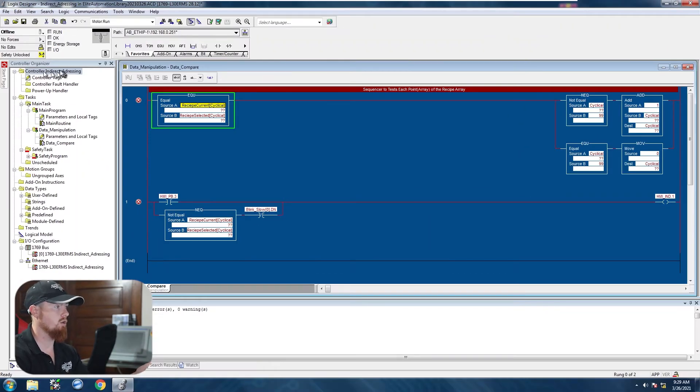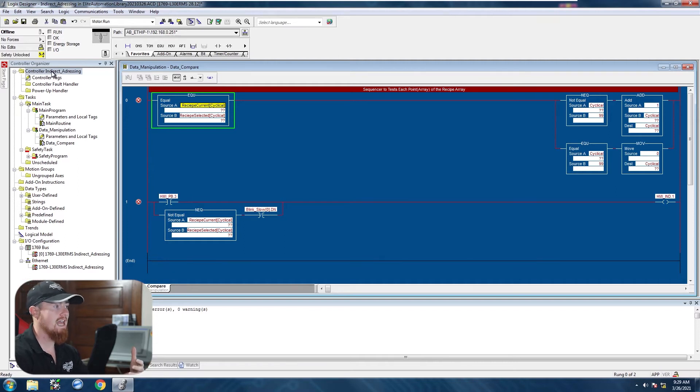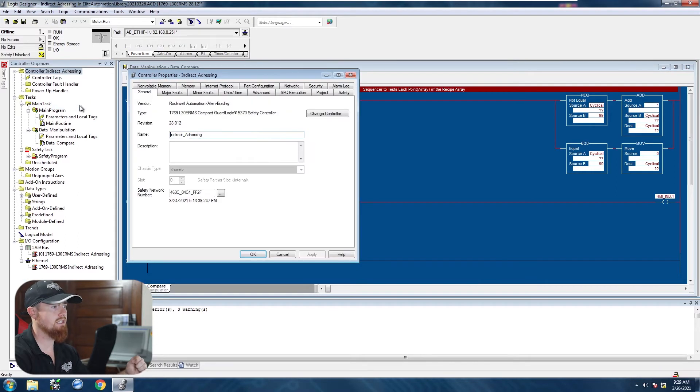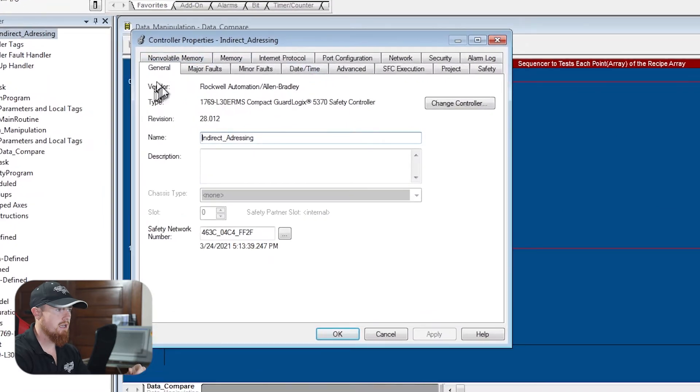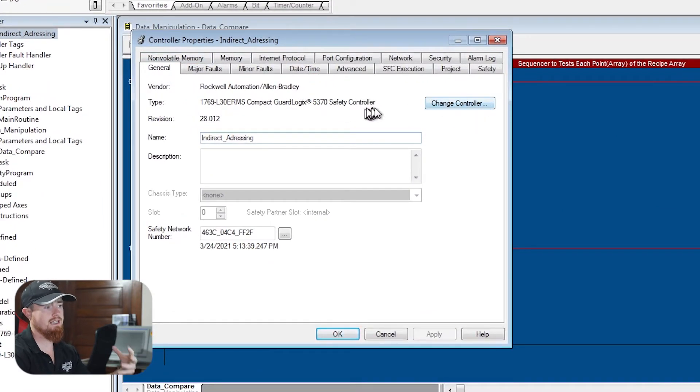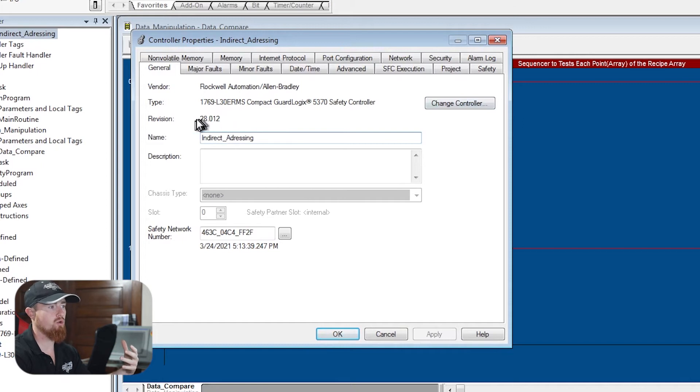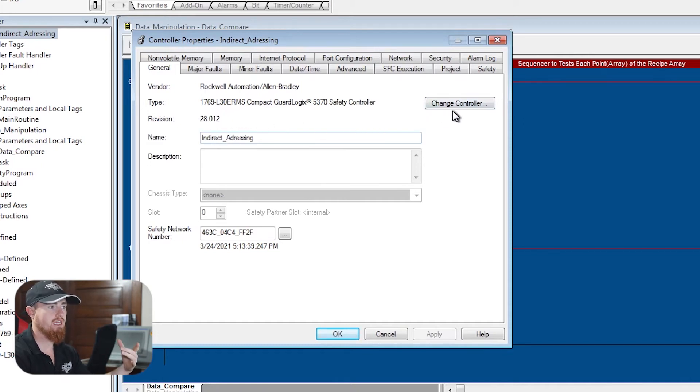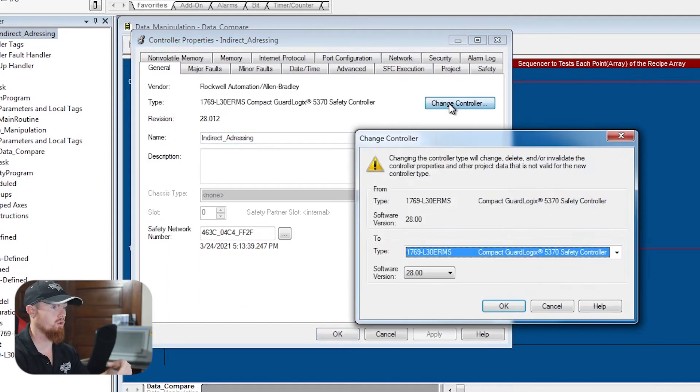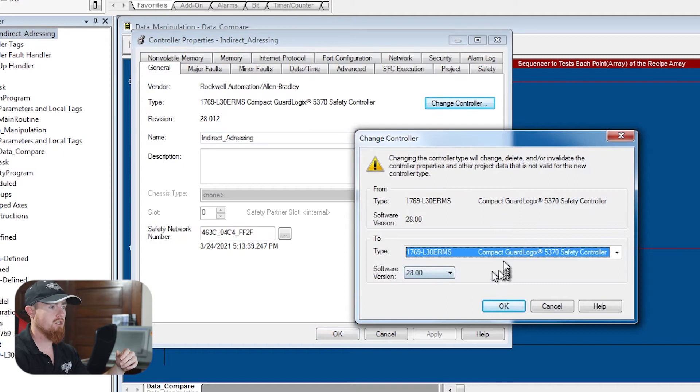We're going to come over here to what your project name is, right click on it, properties. And then we're going to go right here to change controller. See, it's a little bit misleading because it doesn't show you exactly how to change the revision per se. It's saying change controller and you're not really looking to change controller, but that's how you have to go about doing it.